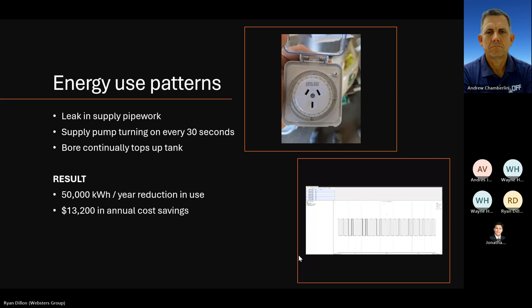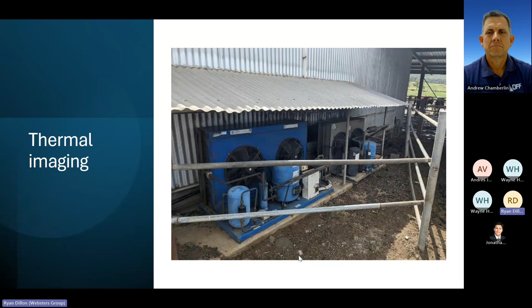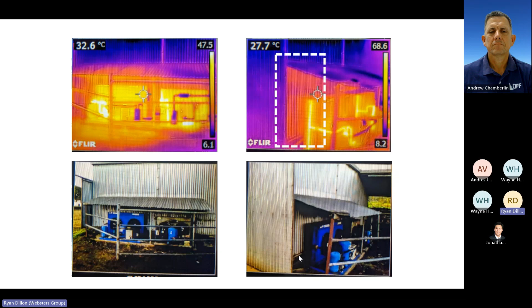Now, this is the refrigeration compressor and condenser that chills a milk vat. So the cows are milked, it goes into a milk vat, it's refrigerated to 3.5 degrees. This provides that refrigeration work, and looking at it, you might not think anything's wrong there. But when we put a thermal camera on it, you can actually see, particularly in the picture in the top right-hand side, the wall behind that condensing unit's quite warm.